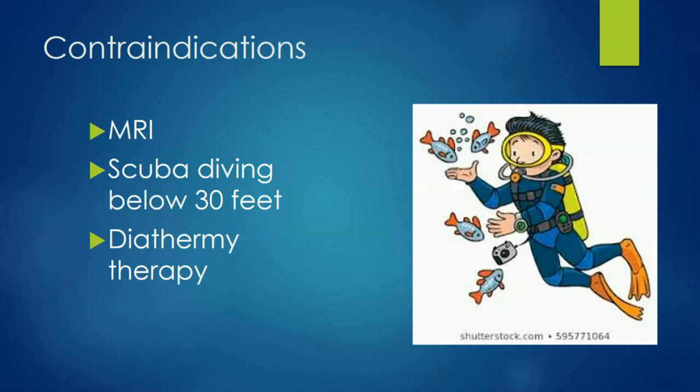So contraindications are MRI below the neck. So you can get a head MR with an Interstim device in place. The concern is that the MR can heat the lead and cause damage to surrounding tissues. Now, I'm going to show you a couple of little case series that suggest that you can do it off-label. I'll just tell you now, and we can skip over that slide, that there's going to be a submission in the fall for an MRI-compatible, full-body MRI-compatible device, with an anticipated approval about this time next year.